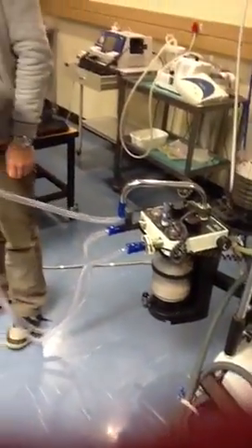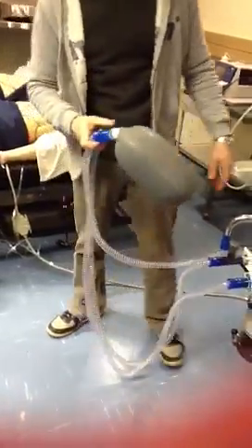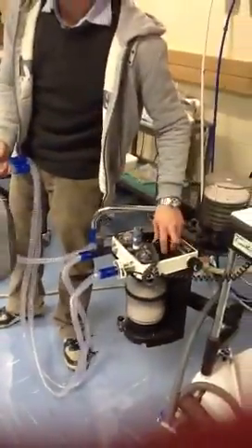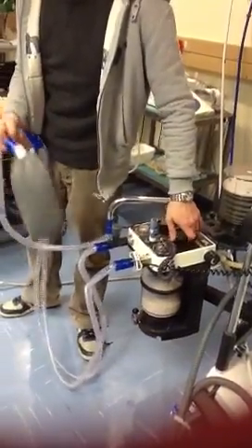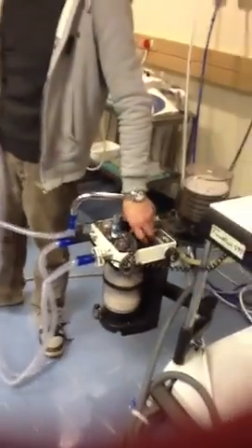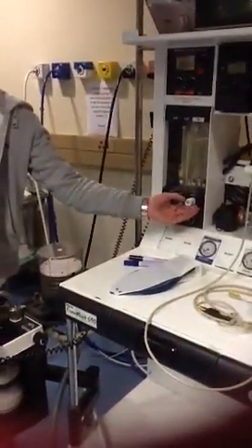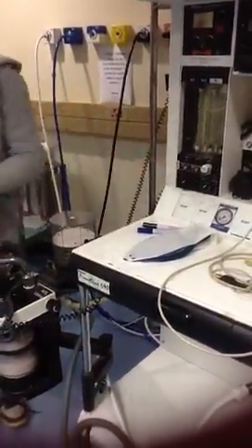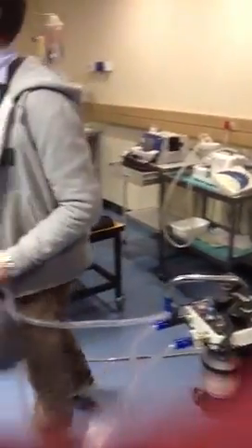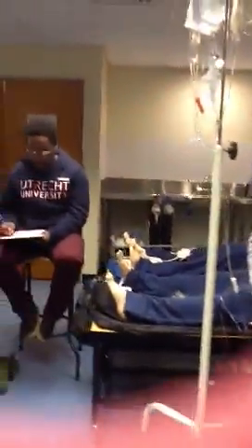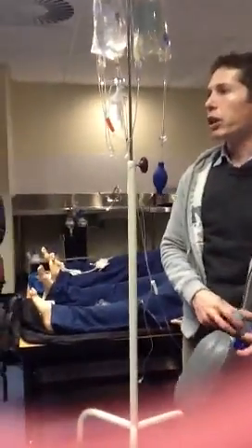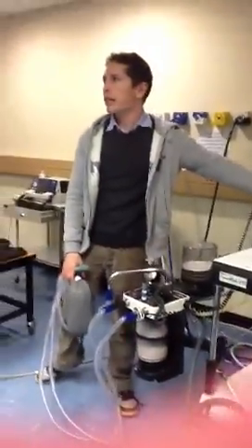Now to efficiently give low flow anesthetics, we obviously don't want the leak to be more than a liter per minute. So all elective surgery we probably delay until we've found out where the leak is. Obviously, if it's an emergency like a stab heart, something that we have to continue, then we'll continue, but we'll have to compensate for that leak all the time.